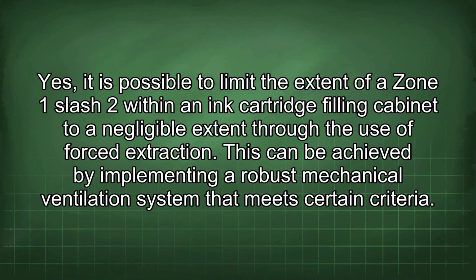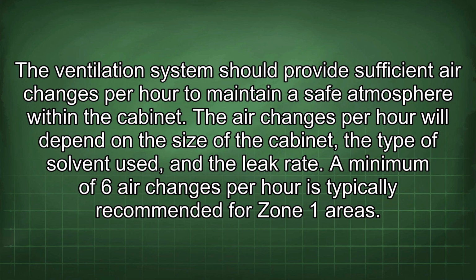Yes, it is possible to limit the extent of a Zone 1/2 within an ink cartridge filling cabinet to a negligible extent through the use of forced extraction. This can be achieved by implementing a robust mechanical ventilation system that meets certain criteria. The ventilation system should provide sufficient air changes per hour to maintain a safe atmosphere within the cabinet.